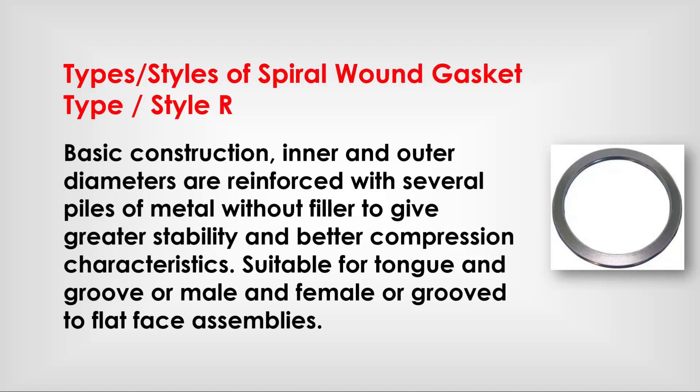Type style basic construction: inner and outer diameters are reinforced with several plies of metal without filler to give greater stability and better compression characteristics. This style is suitable for tongue-and-groove, male-and-female, or groove-to-flat-face flange assemblies.